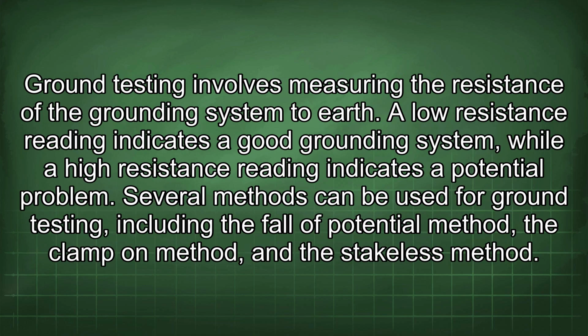Ground testing involves measuring the resistance of the grounding system to earth. A low resistance reading indicates a good grounding system, while a high resistance reading indicates a potential problem. Several methods can be used for ground testing, including the fall of potential method, the clamp-on method, and the stakeless method.